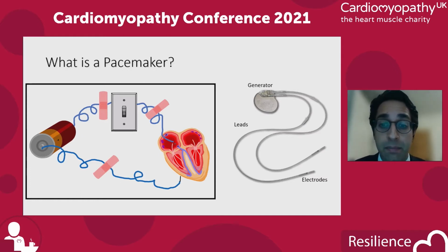But of course, all of this needs a battery, and the technology for that still is maturing. And so the key components of our pacemakers are the generator, which contains the on and off switch for triggering when the heart should beat, the battery, which is contained in the box of the generator. Then you've got the leads, and you can see on the picture on the other side of the screen that there's two leads, one to the top and one to the bottom of the heart. And the reason for that is the filling chambers at the top of the heart need to synchronize with the lower pumping chambers of the heart.